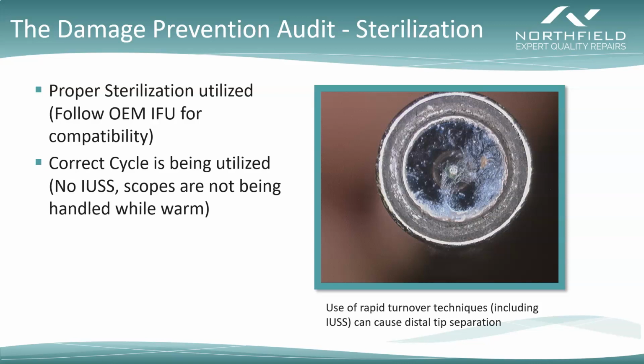A good indicator on that question is, how often are you having to rapidly turn over scopes? If you find that there are scopes that you are having to turn over frequently, that's an indication that you might need to get some more scopes. Now, I know that this is very counterintuitive, especially for a lot of administrators, to think that you can actually save money by spending more on your inventory. But if you don't have enough scopes, you're going to hurry during the reprocessing. And if you're moving warm scopes into a cold OR and then into a warm body, that's going to lead to this exact type of damage.